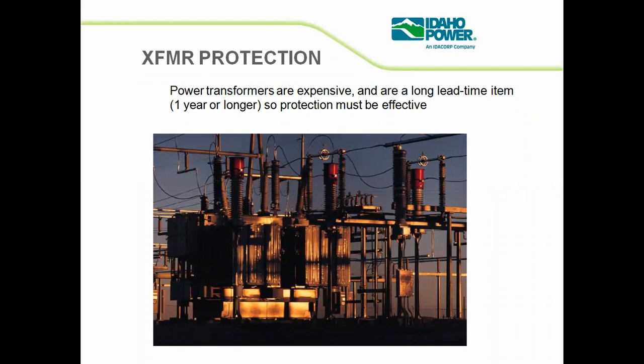Now you can see in today's scenario, frequently our transformers are getting damaged. The very important reason is overheating, because already the outside temperature is very high, and in addition to that you are using power at a very high rate. So the temperature of the winding of the transformer increases day by day, and when it reaches a certain level, your windings will get damaged, and ultimately your transformer will get damaged. So you have to protect the transformer against this overheating.